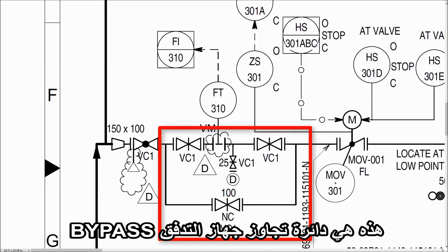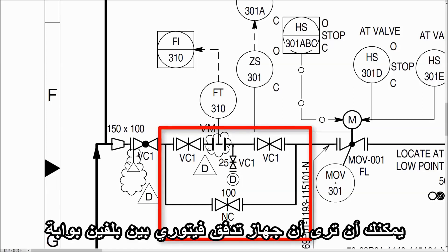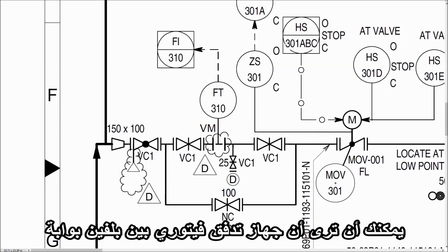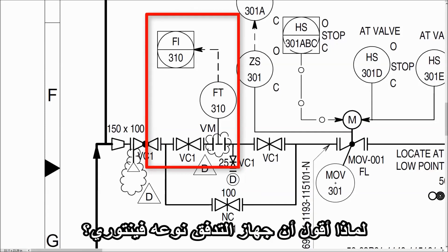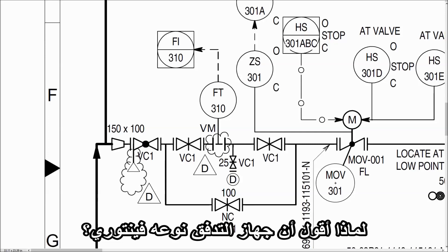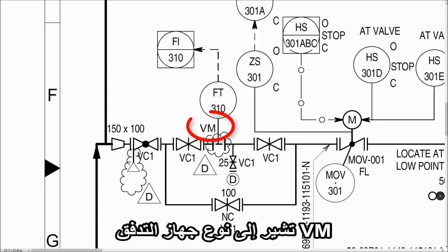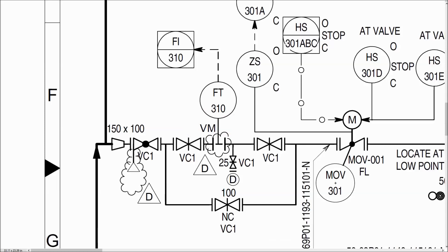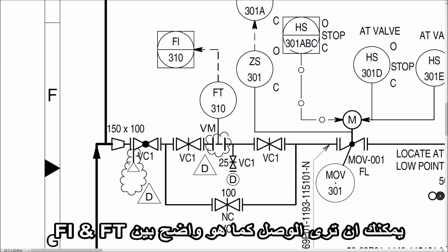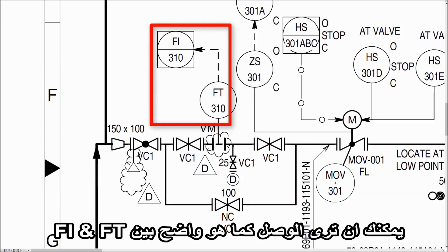This is the bypass loop for the flow transmitter. You can see that a Venturi type flow meter is provided in between the two gate valves. The letters VM indicate the type of flow meter. It gives flow indication on the control panel. You can see the connection shown between FT and FI.